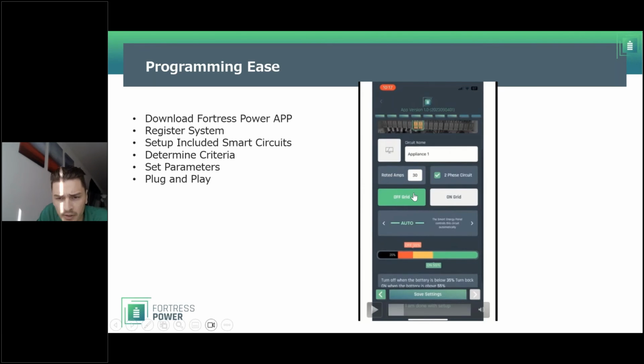So off grid, it says the smart energy panel controls this circuit automatically when off grid. As we go through this, you can set different thresholds for when to turn on and off that circuit based on the battery power. This is saying turn off the battery, or turn off when the battery is below 45, and turn back on when the battery is above 78%, through this slider with the red, yellow, and green colors.